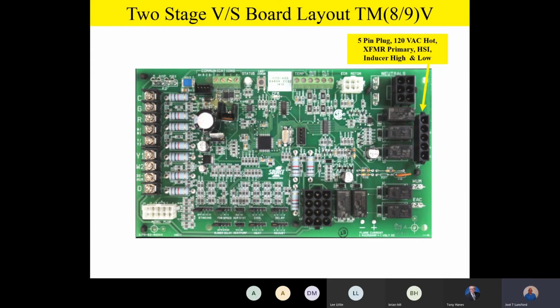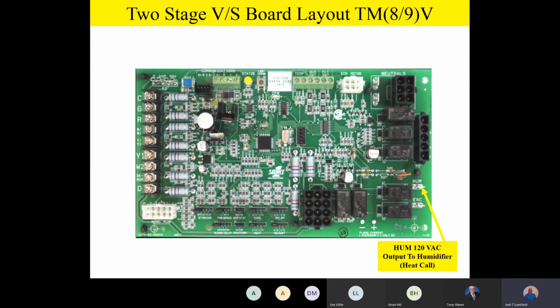As you move down the side of the board, team, you're going to notice there's a humidifier terminal. Again, that's 120 volt, to operate a humidifier anytime we have our heating call, if you want to power your humidifier right off the board. And let me say something about this too while I'm on this line of thinking. One of the things that's kind of cool about the Champion furnaces is, you don't have to have a lot of accessory boards and stuff to hook up some of the common things that you're going to see out there in the industry. For instance, like a humidifier, an electronic air cleaner. You don't have to run special power sources or anything like that. A lot of that's controlled right on our board.